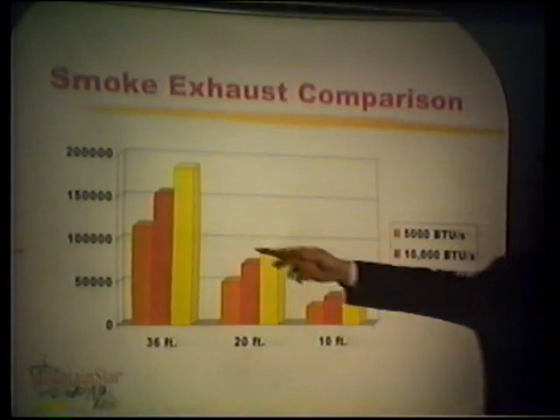As I mentioned in that first graph, if we looked at that sprinkler analogy, that we hit it at a much smaller size, if you look at this chart, if we had a 10-foot high ceiling and we had a 5,000 BTU fire, 10,000, and the yellow is 15,000, you can see the smoke exhaust on the vertical axis. As the fire gets larger, we have more CFM that we would have to exhaust. And even not changing the fire sizes, but just changing the height of the building, look at the differences in the smoke exhaust capacities. Just by changing the height.